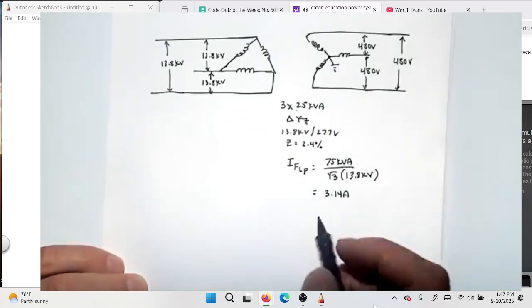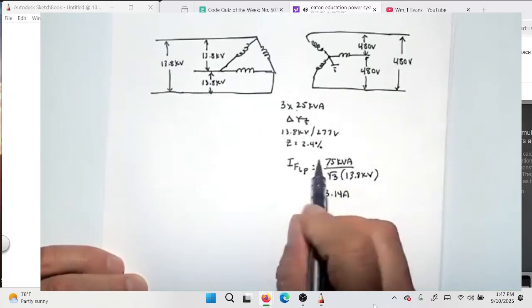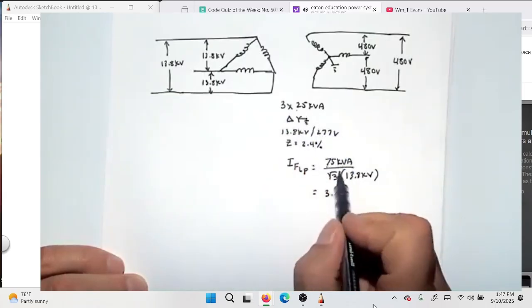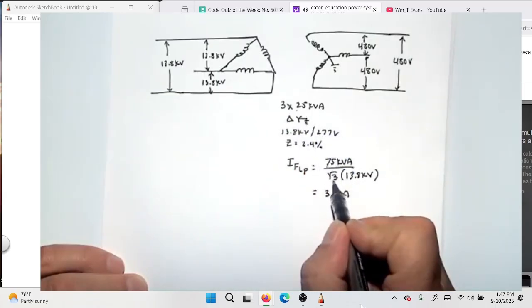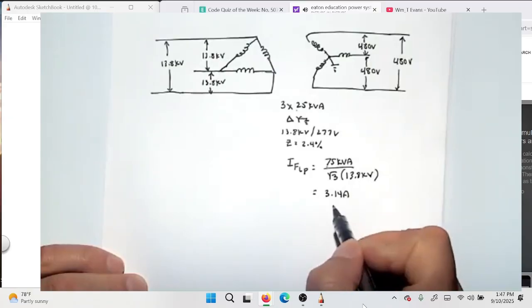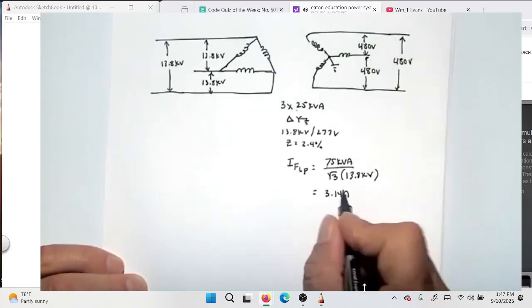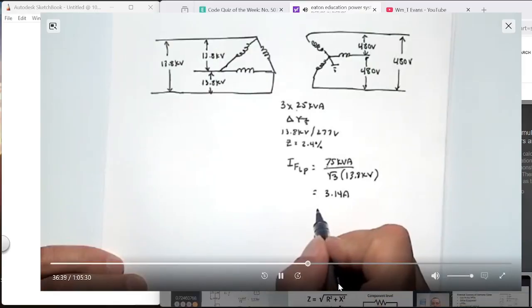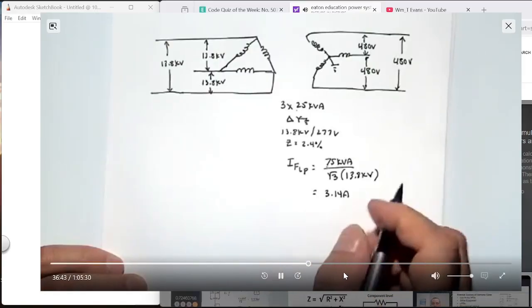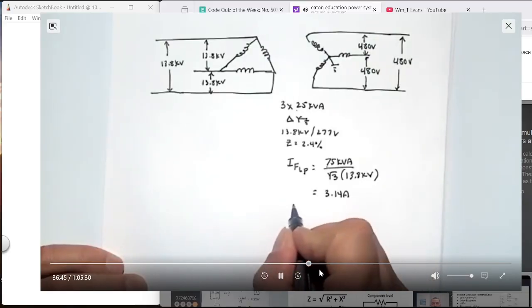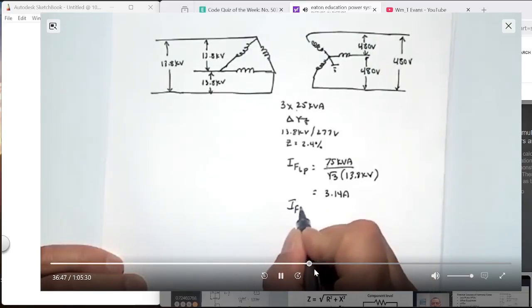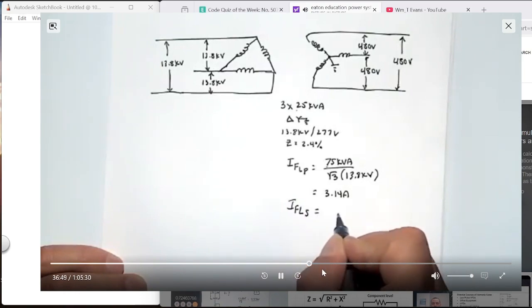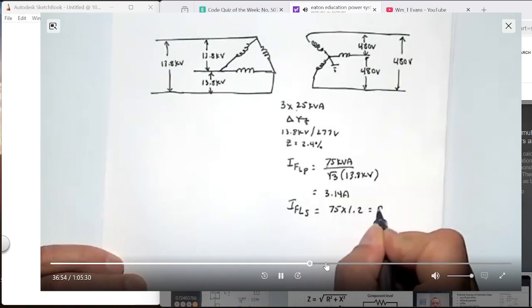So here's our neutral point on the secondary of the transformers. 480 volt line to line on the secondary. So our difference in our calculation really is we're going to take this 3 times 25 kVA and make it a 75 kVA transformer. There's our square root of 3 and 13.8 kV. That works out to be about 3 amps. So again, even though the wire size could be very, very small, in this case, we only need about 3 amps on the primary. And on the secondary, again, we already know what that's going to be. It's going to be 75 times 1.2, or about 90 amps.